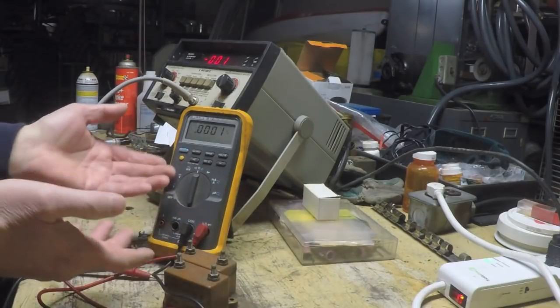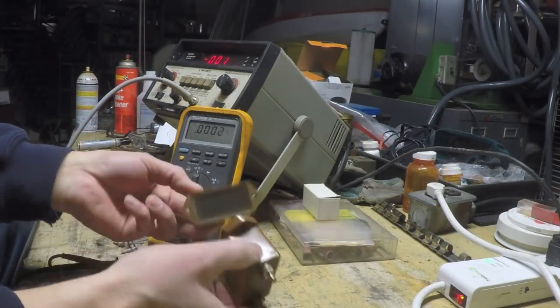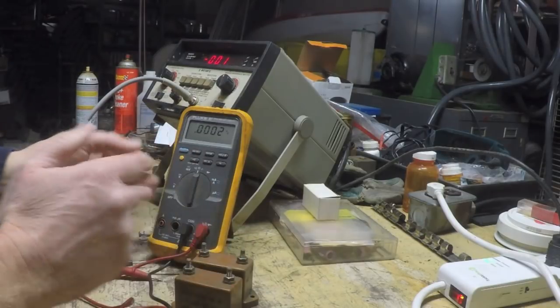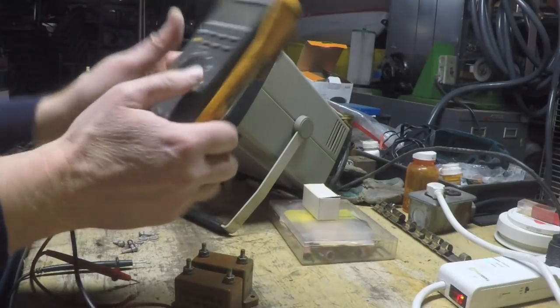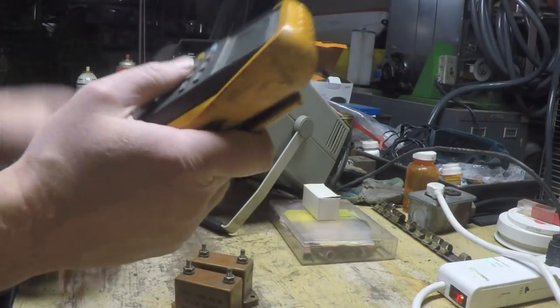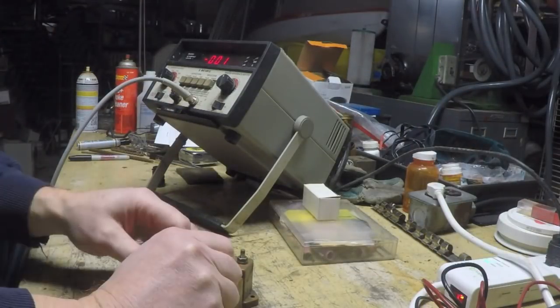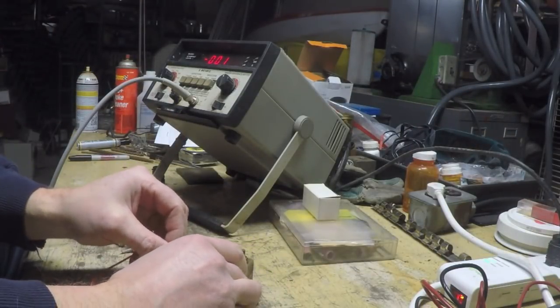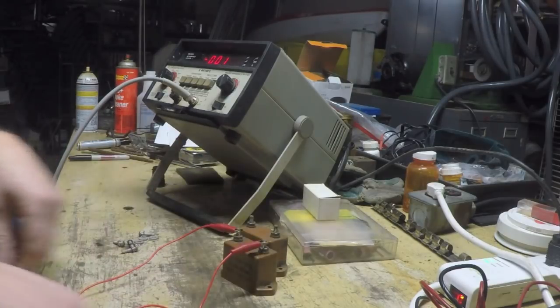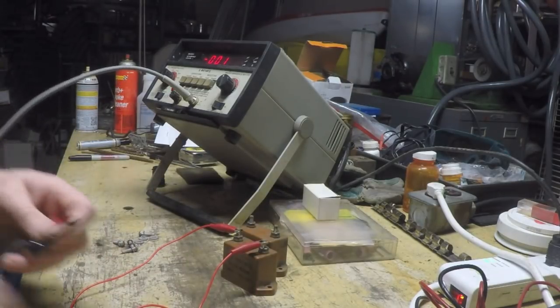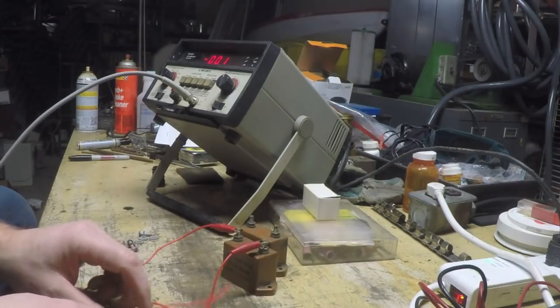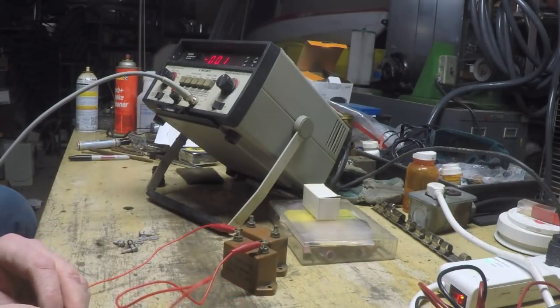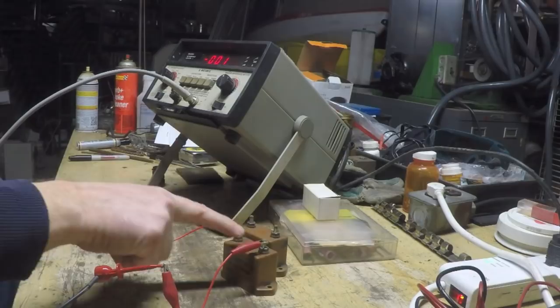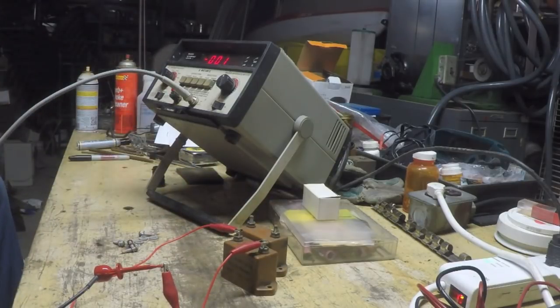So again, what did I show? I showed that these are measuring the correct value of capacitance, but this doesn't prove anything, because maybe they don't start to break down until a couple thousand volts are applied. I can only put 600 volts across this thing, which might not be enough to get it to break down. But I am interested in what the leakage current measures. If there's a big difference from this one to this one, that might indicate a problem.